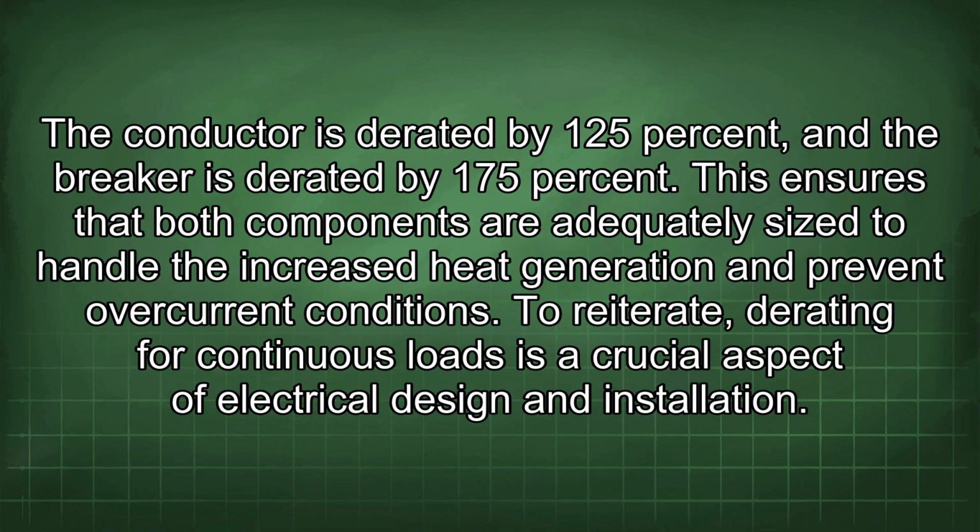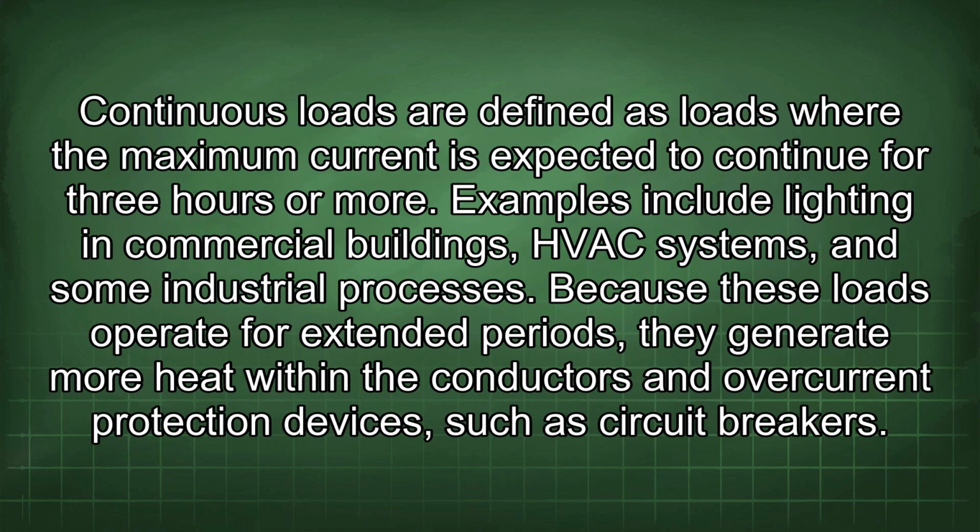To reiterate, derating for continuous loads is a crucial aspect of electrical design and installation. Continuous loads are defined as loads where the maximum current is expected to continue for 3 hours or more. Examples include lighting in commercial buildings, HVAC systems, and some industrial processes.